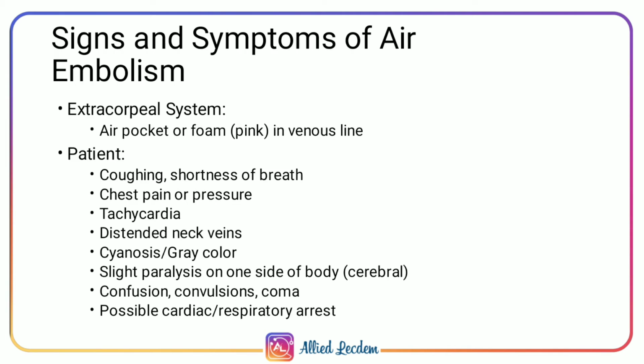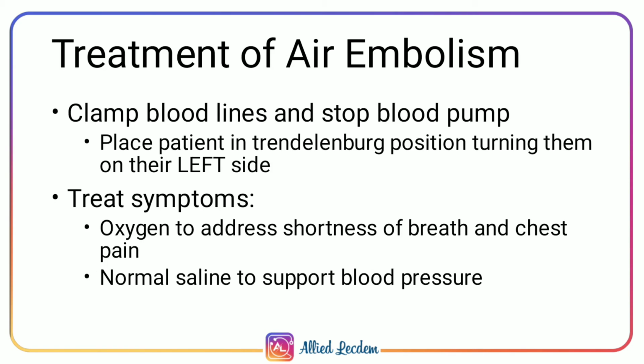Signs and symptoms of air embolism: in the extracorporeal system, air pocket or foam in venous line; in the patient, coughing, shortness of breath, chest pain, tachycardia, cyanosis, confusion, possible cardiac or respiratory arrest.